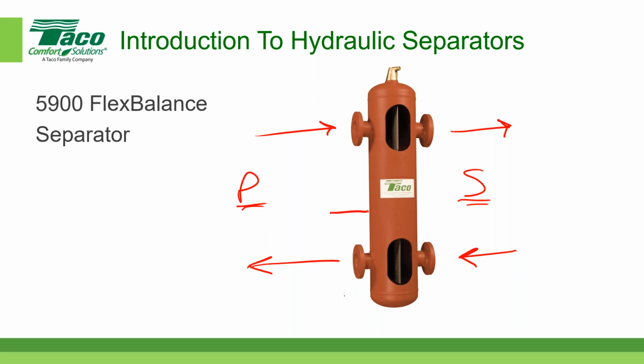I'll just sketch that out here. Say the diameter of the hydraulic separator, the distance between the inlets and the outlets here. And if you notice inside this cutaway, we have a little baffle. So a pre-engineered device takes into consideration, oh, and the other critical dimensions are from the total length of the hydraulic separator to the connection. So all of these different dimensions are important in terms of their design for the hydraulic separator to work properly.